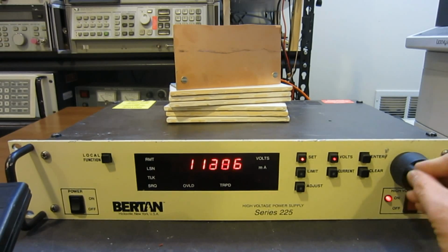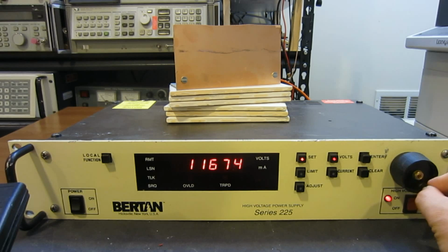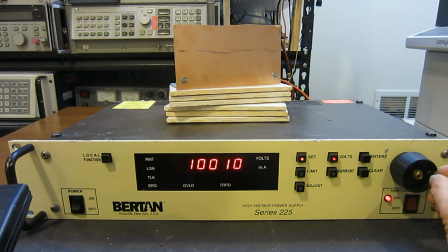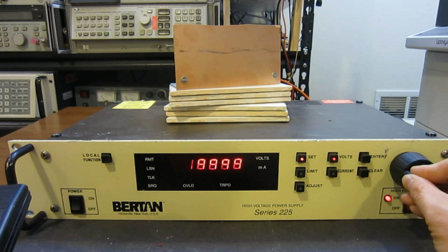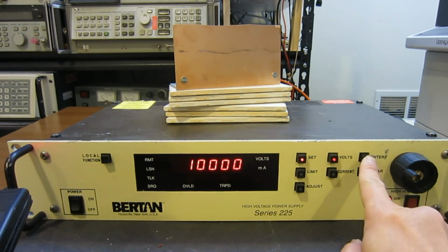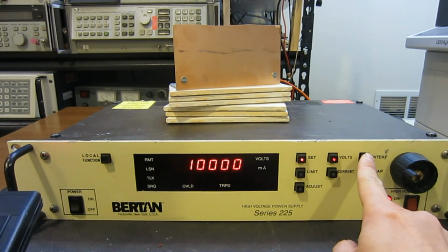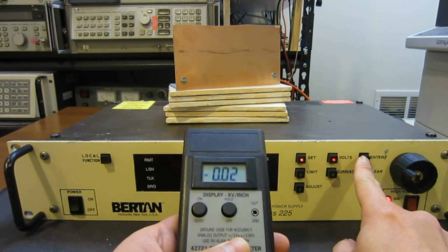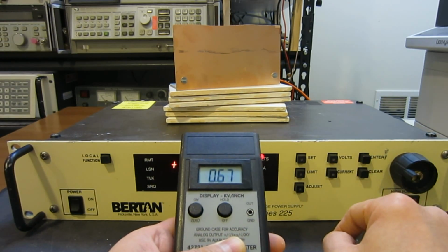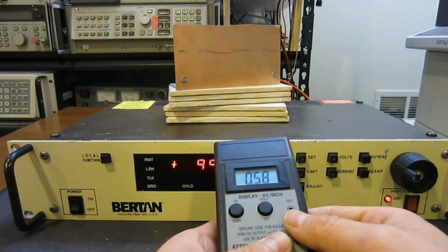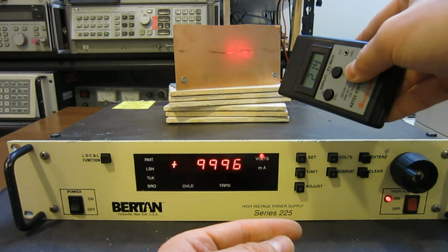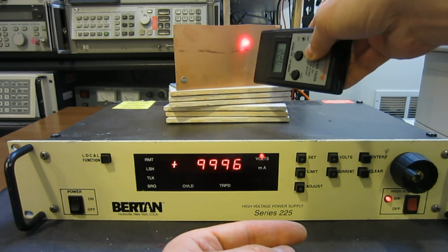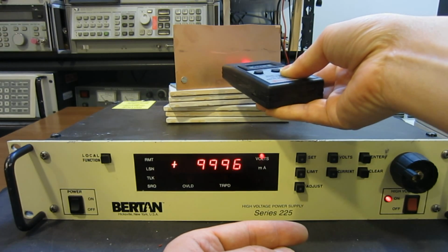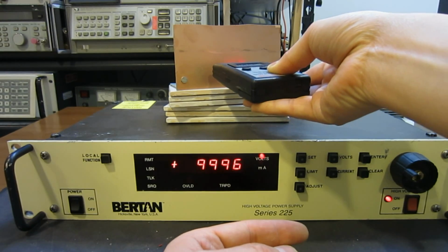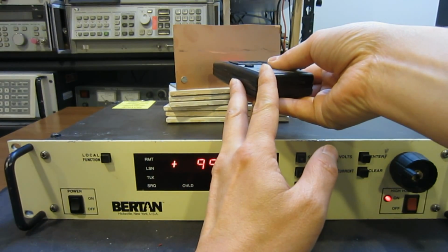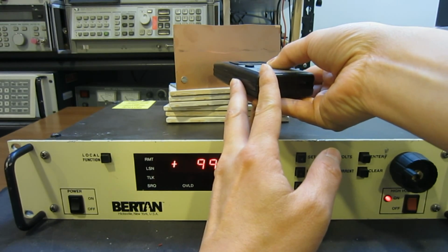Okay, so let's set it to 10,000. It doesn't need to be that accurate. Okay, 10,000. Now as soon as we hit enter, that plate will be energized. Okay, so now we hit enter. So let me just put this here. Okay, so now enter. And you can see already we are picking up some readings. But as I move this closer, I'm going to try to let you still see the reading here. I'm going to do a hold on that. So this is roughly 1 inch. Okay, so now I'm going to do a hold.